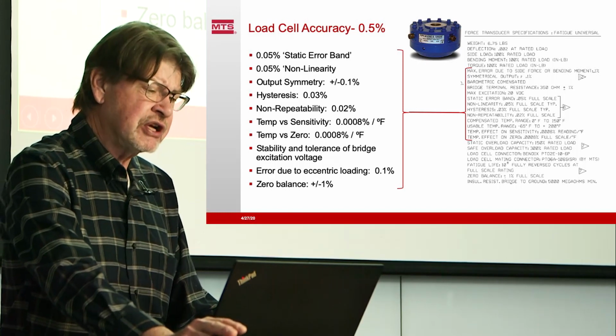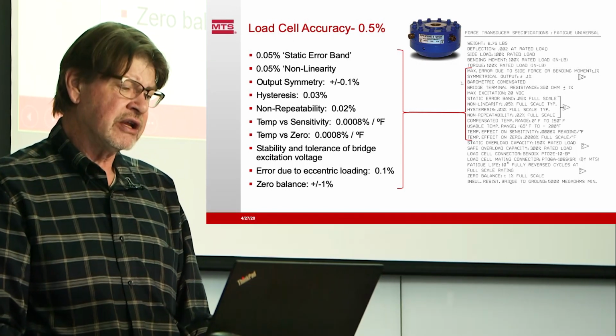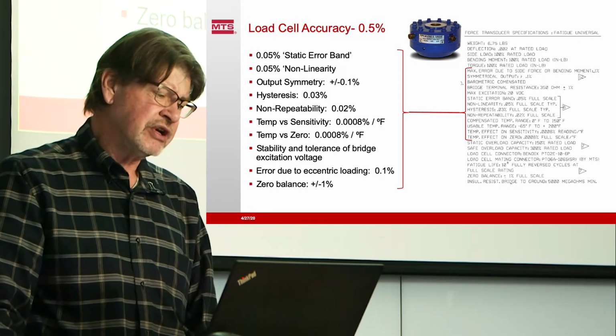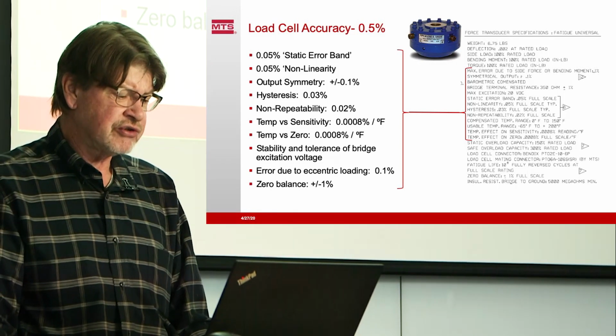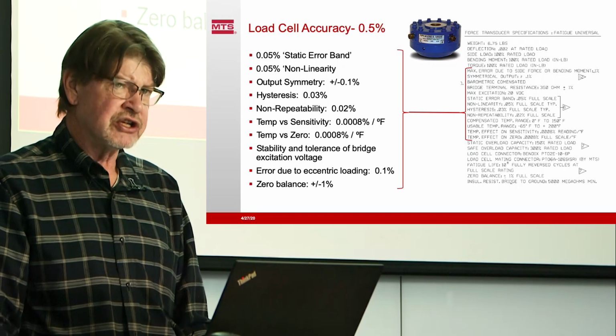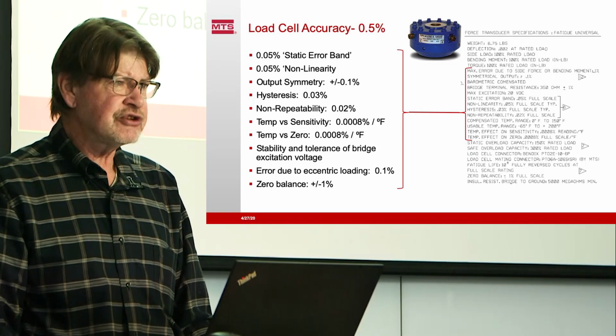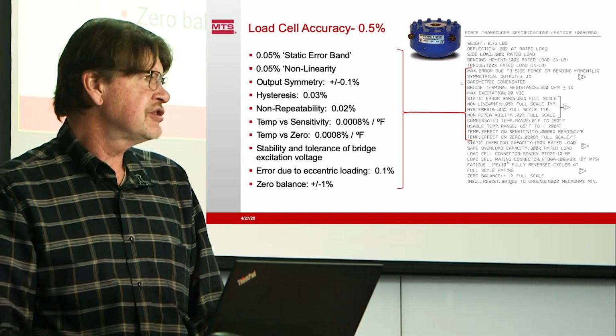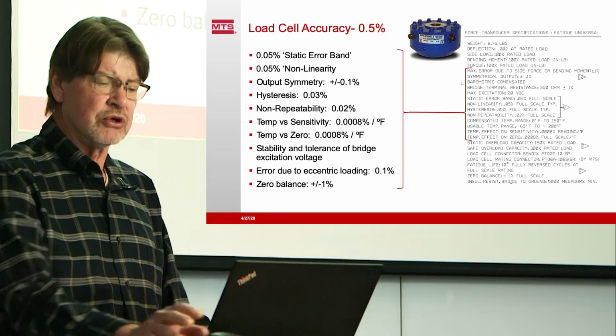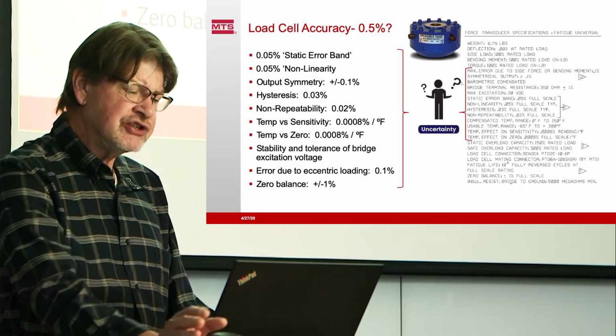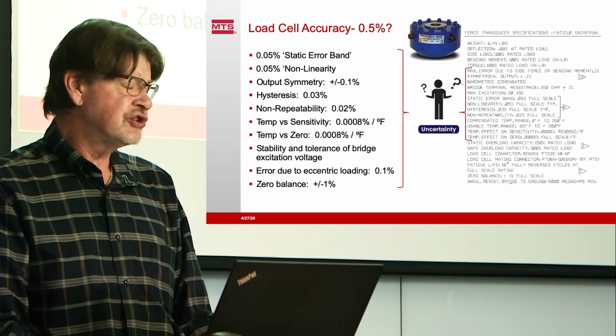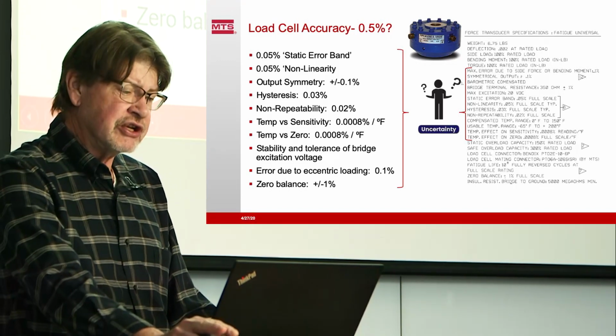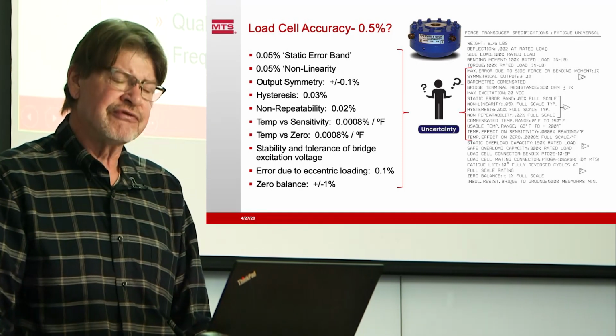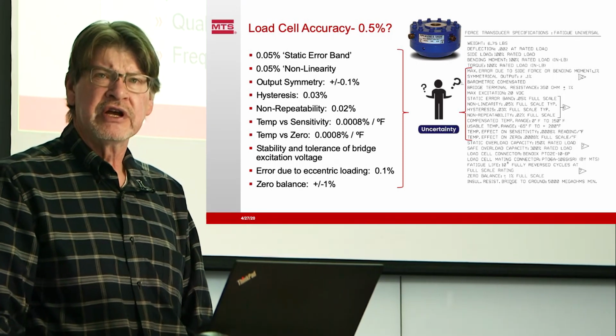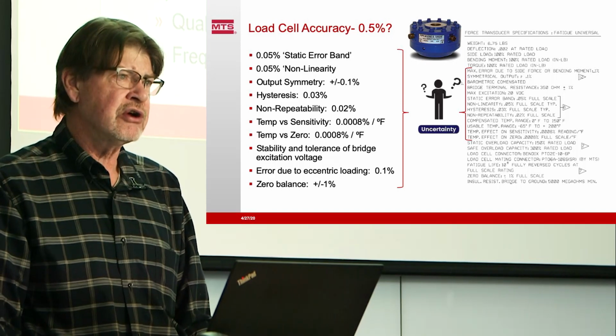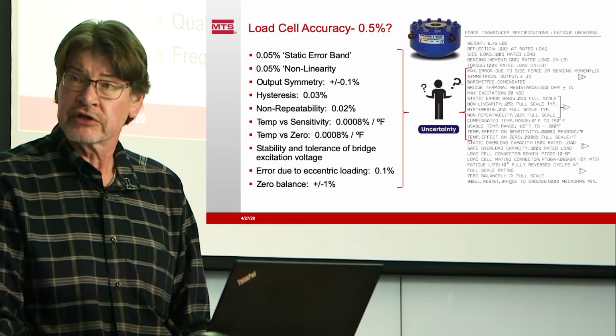Here we've got all of these potential sources of error: static error band, nonlinearity, output symmetry, hysteresis, non-repeatability, etc., down to zero balance plus or minus 1%. Some of these things we can compensate in the electronics, some of these things are uncompensated and uncompensatable. And so what does that lead to? That leads to a certain level of uncertainty in the load cell output. And so it's an intelligent thing for us to do to figure out how much that uncertainty is, and keep in mind that it's a potential error in our output and potentially our conclusions.